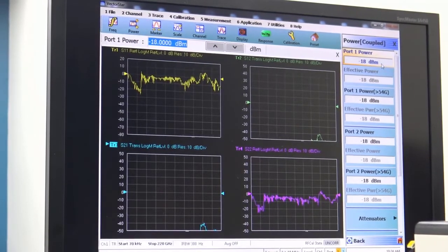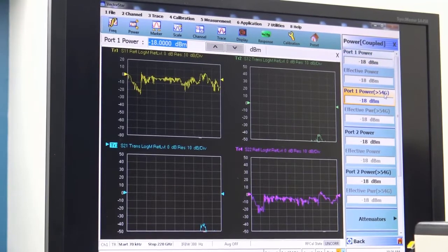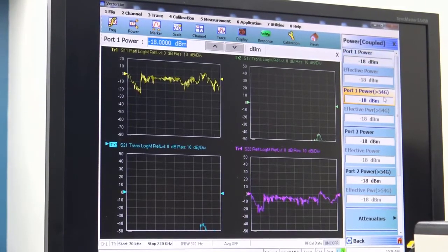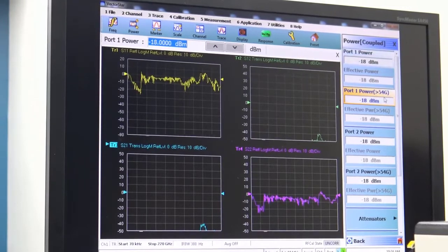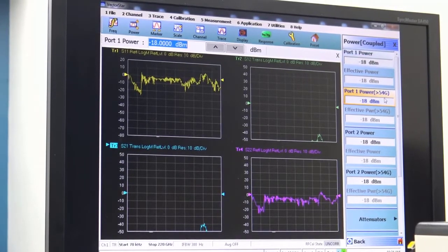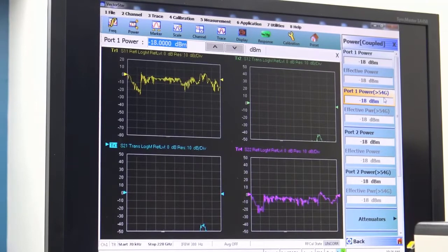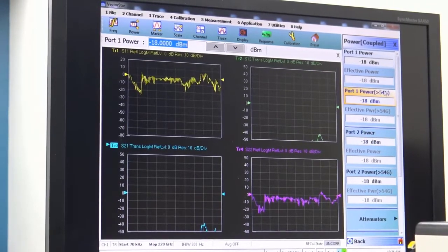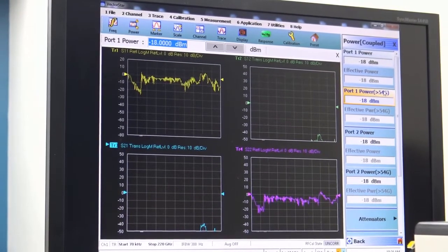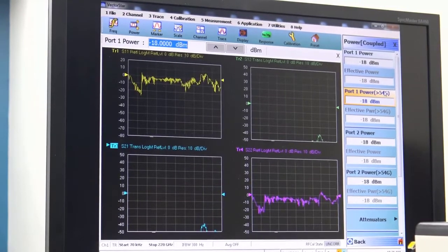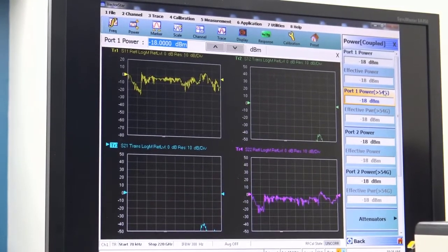And next we could go to power and set our power for both the low band and high band. So up to 54 gigahertz is the low band, that's set for -18, and above 54 we're also set for -18 to go all the way up to 220. And the same is true for port 2 in terms of the low band and high band power. So we're set for a -18 dBm broadband sweep from 70 kilohertz to 220 gigahertz.